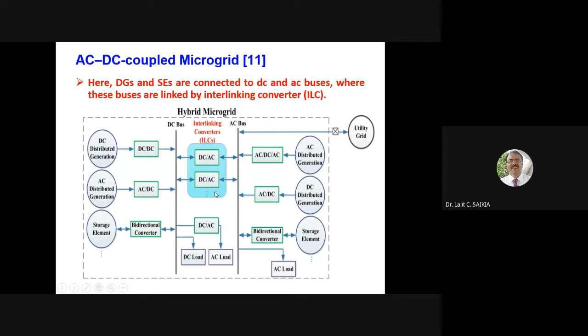Grid interfacing converters work like this. The main objective of this control is fulfilled by accurate P and Q sharing among the user units by incorporating power controllers, mainly controlling the voltage source converter terminal voltage magnitude and frequency using the voltage controller, and achieving required filter inductor current by applying the current controller. Hence this primary control provides internal control of the converter output voltage and current, as well as power sharing using centralized or decentralized control technique.